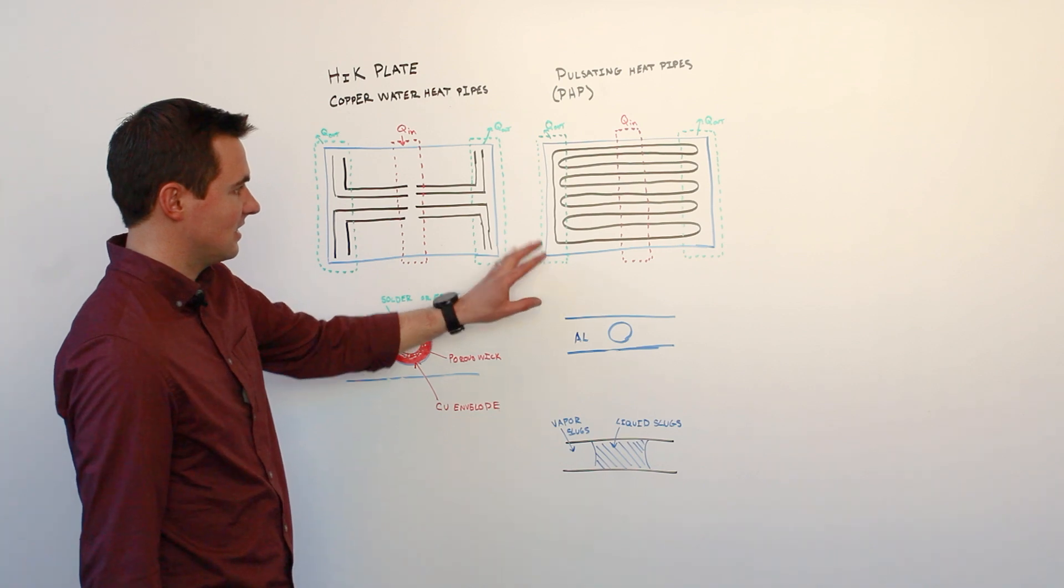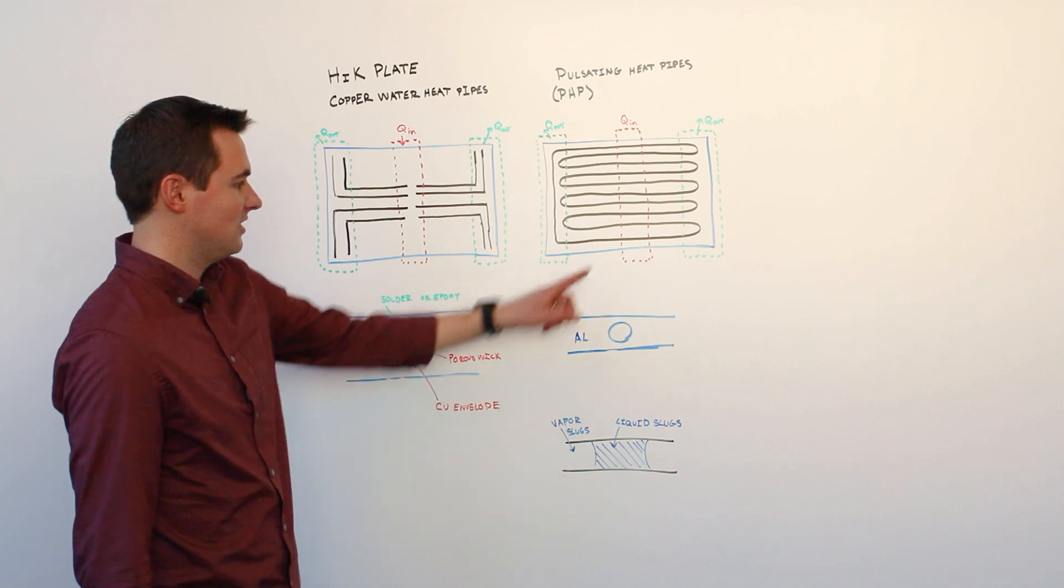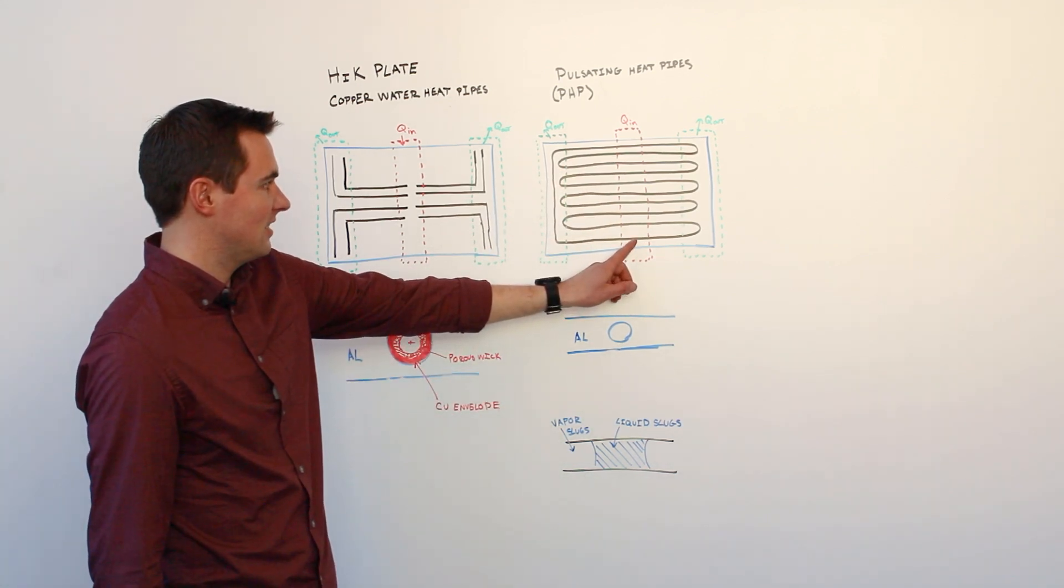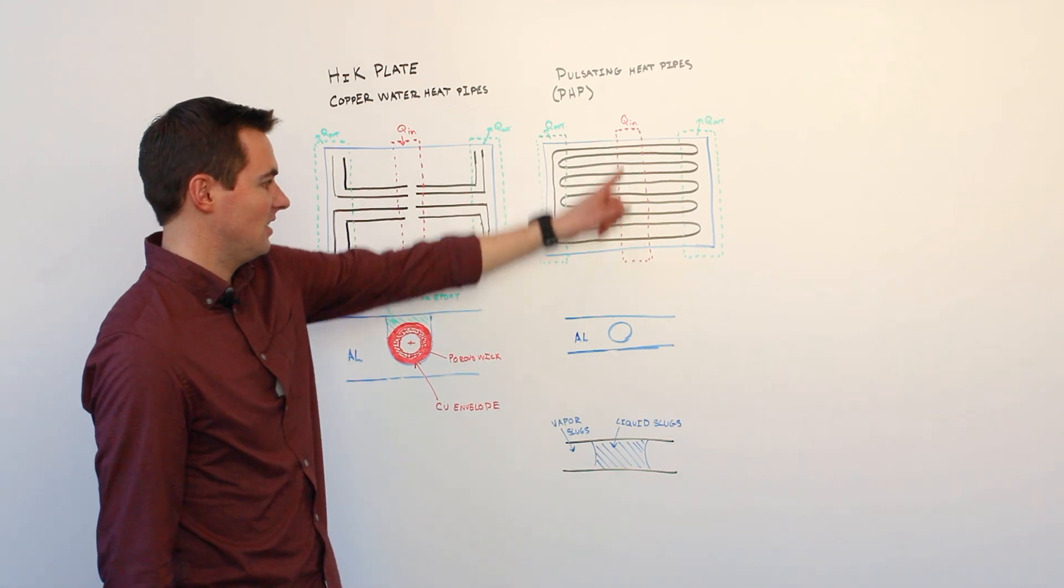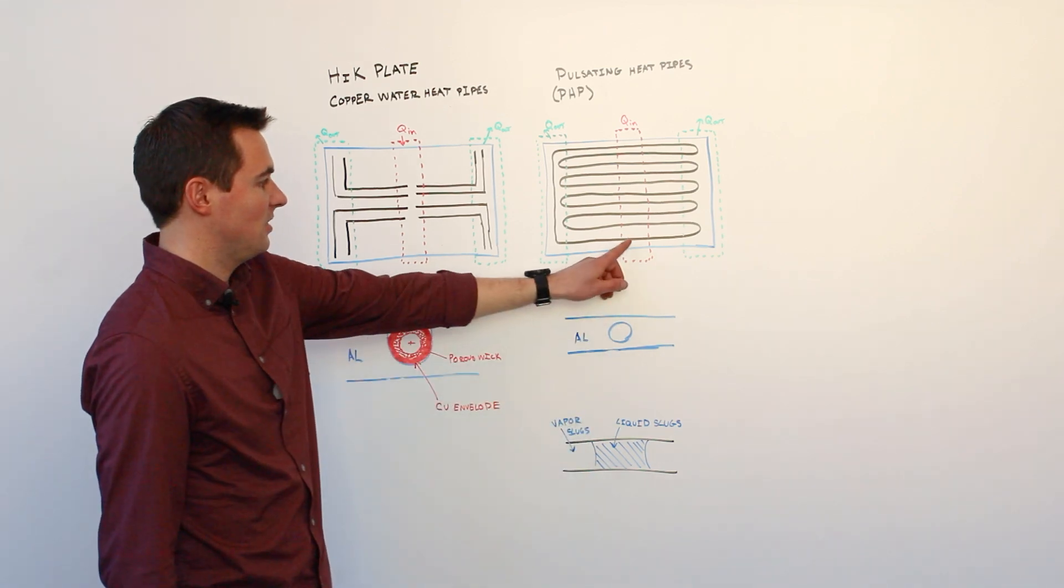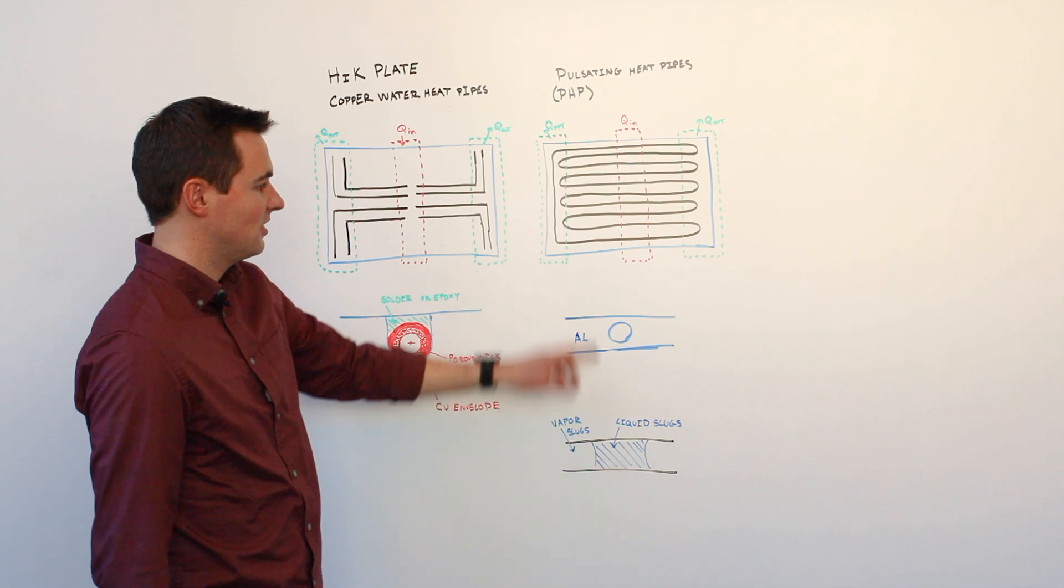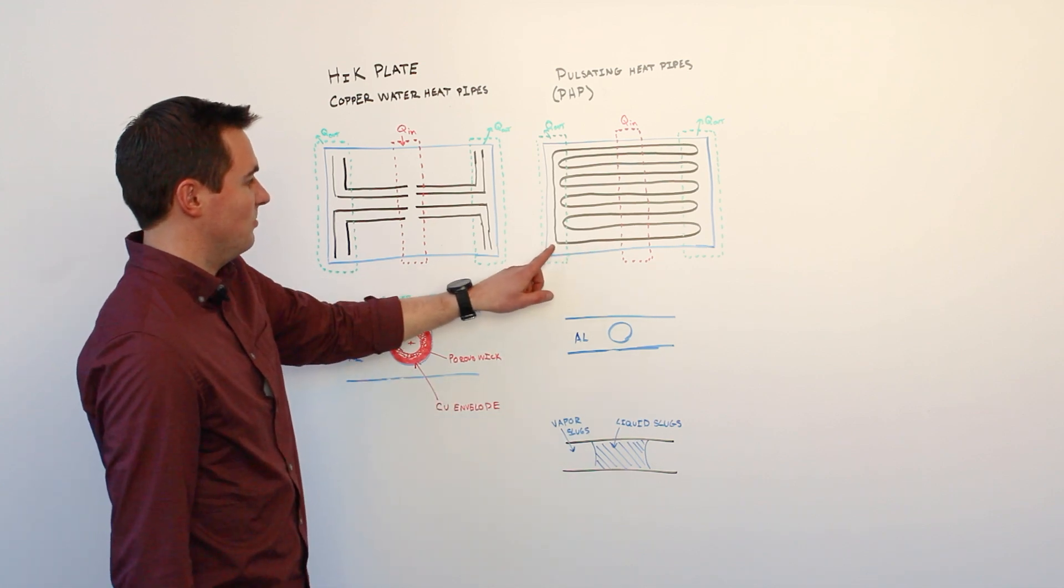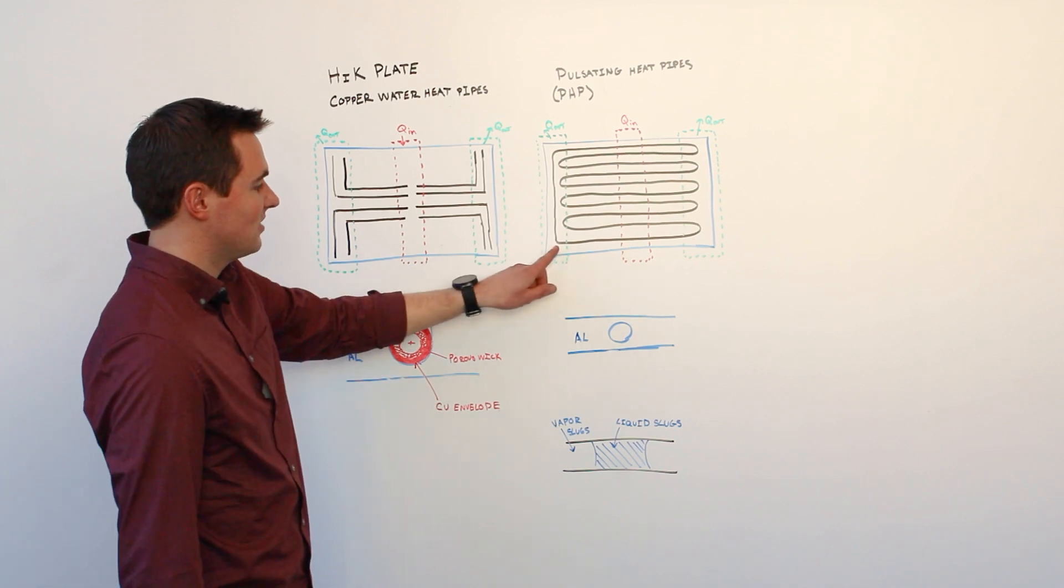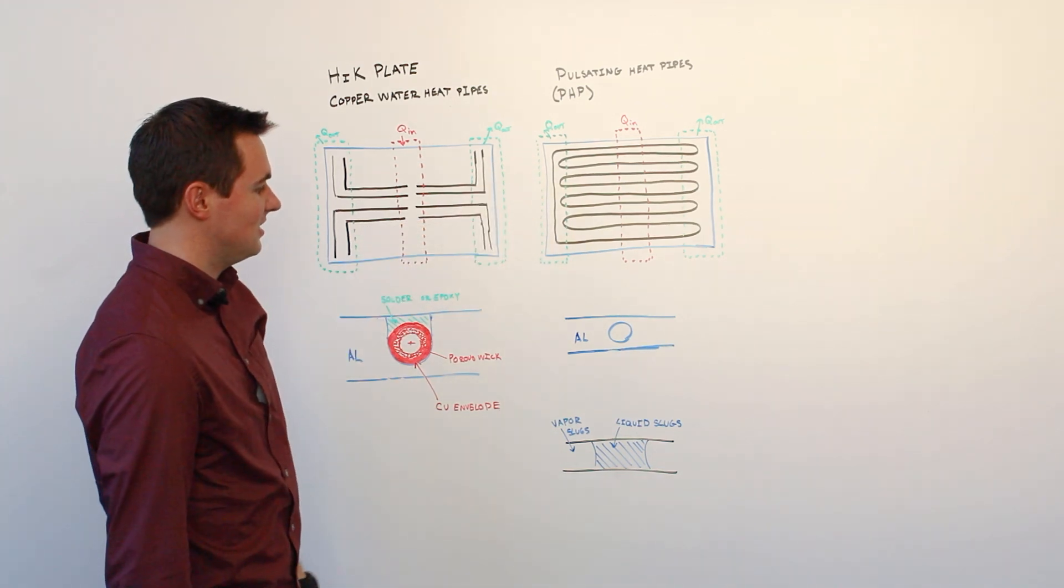This technology works somewhat differently where we have liquid slugs and vapor slugs distributed throughout the channel. When liquid slugs occupy this region in the evaporator, some of this liquid will vaporize causing high pressure which pushes other liquid slugs to the cold side and therefore transfers heat to your condenser regions.